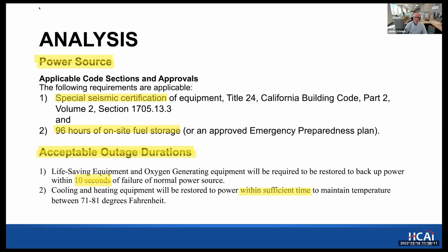So just a quick analysis: the new resources to meet this bill's requirement are going to need to be specially certified, seismically certified, and have 96 hours of on-site fuel storage. We've identified in the PIN that life-saving and oxygen generating equipment would need to come back up on power in the event of a power failure within 10 seconds, leaving it up to the engineers to determine the time required to bring the HVAC back online to maintain the temperature.